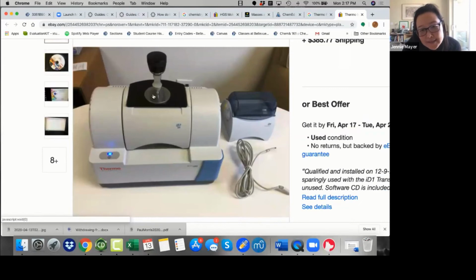It's got a little disc here, the laser's inside, and it's got a diamond crystal right in the center where that thing is clamped down. So basically, we have this version where instead of passing the light through the sample, we pass it up into a diamond crystal. Then it interacts with your sample and bounces through the crystal and then goes to the detector.